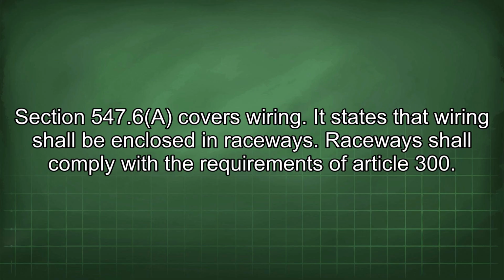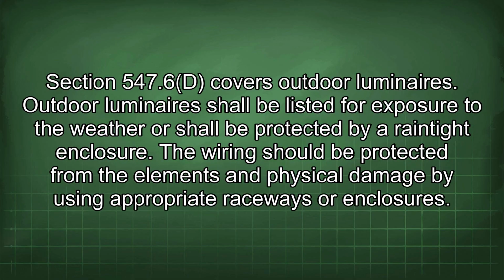Section 547.6 covers wiring. It states that wiring shall be enclosed in raceways. Raceways shall comply with the requirements of Article 300. Section 547.6d covers outdoor luminaires. Outdoor luminaires shall be listed for exposure to the weather or shall be protected by a raintight enclosure. The wiring should be protected from the elements and physical damage by using appropriate raceways or enclosures.